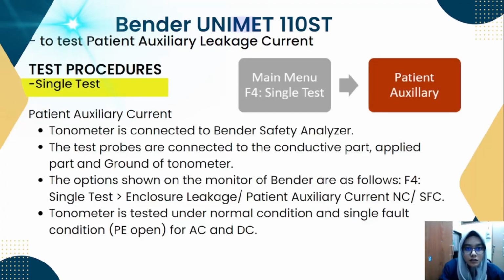Next, to test the patient auxiliary leakage current, Bender single test is conducted. Same as before, the tonometer is connected to the Bender safety analyzer, then we have 3 probes connected to the conductive part, applied part, and the ground of the tonometer. Then, the option of single test is chosen from the monitor of the Bender. Then the tonometer will be tested under the normal condition and single fault condition for the AC and DC.